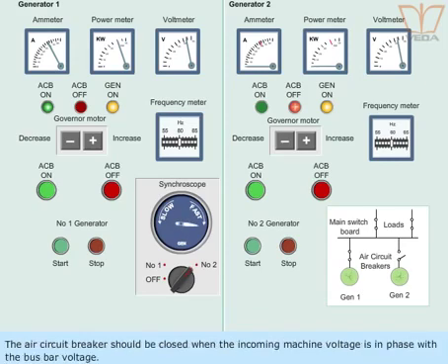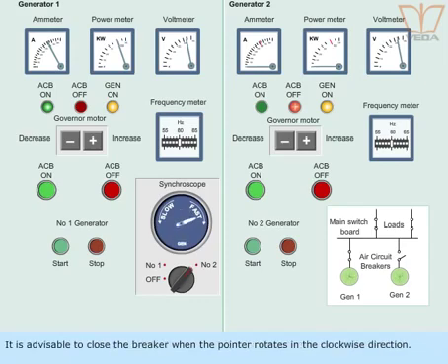The air circuit breaker should be closed when the incoming machine voltage is in phase with the bus bar voltage. It is advisable to close the breaker when the pointer rotates in clockwise direction.